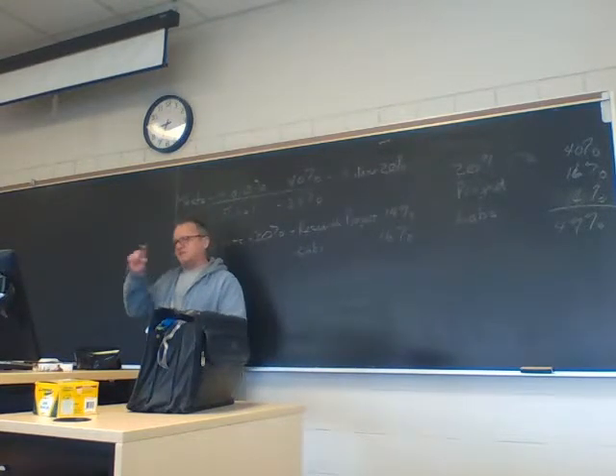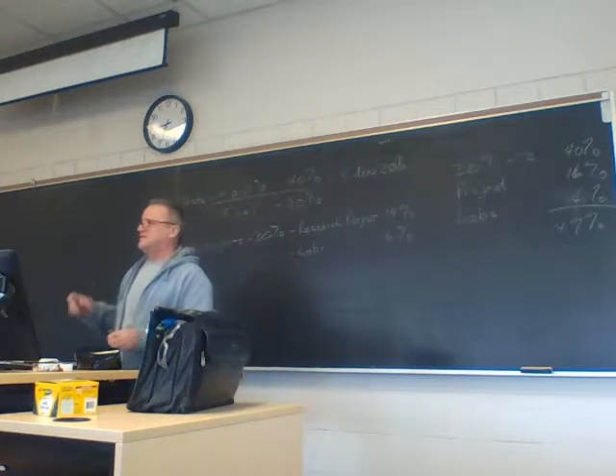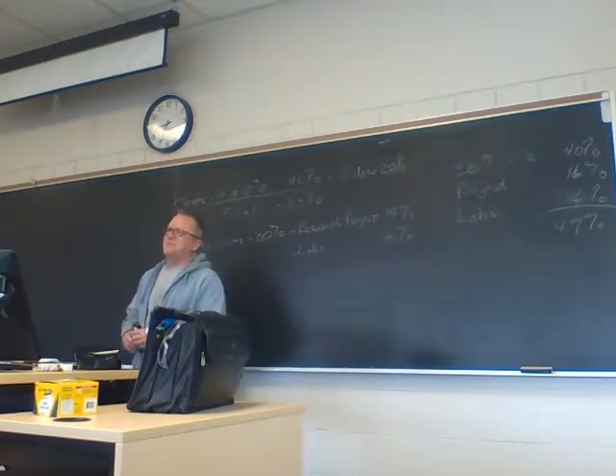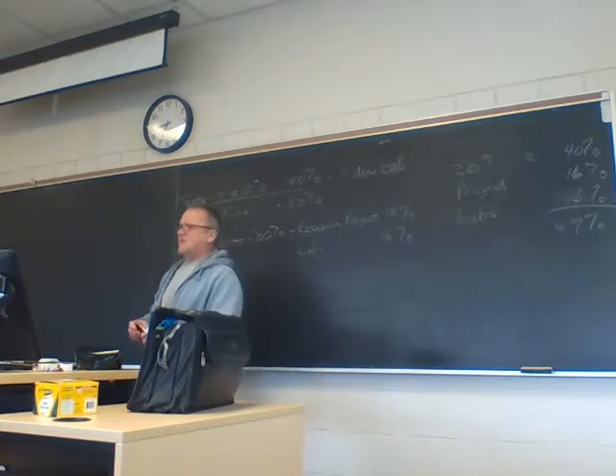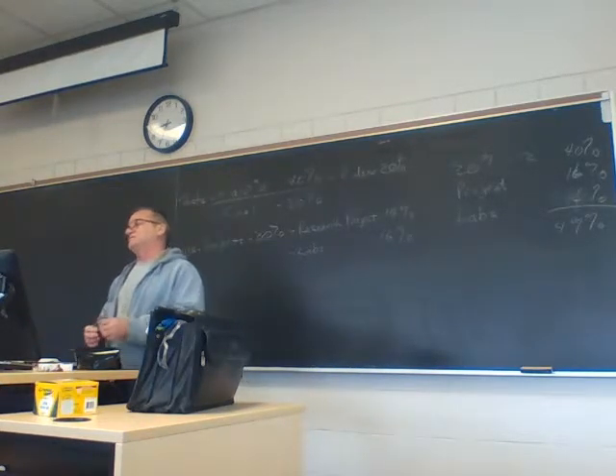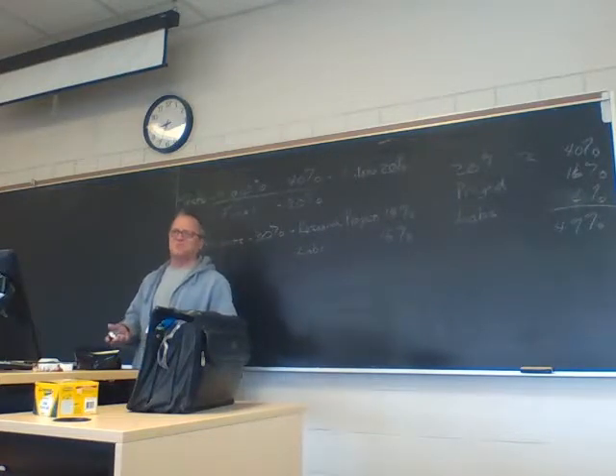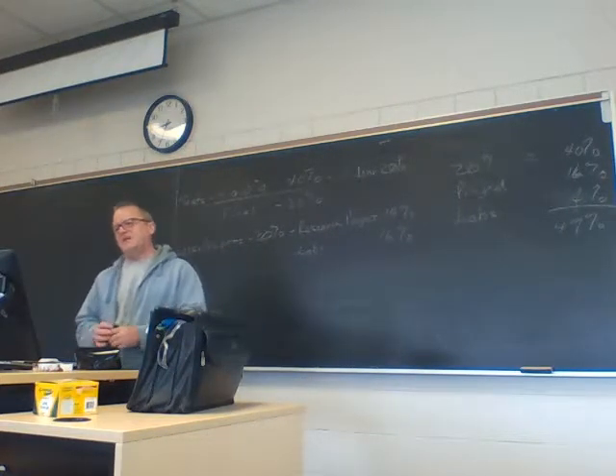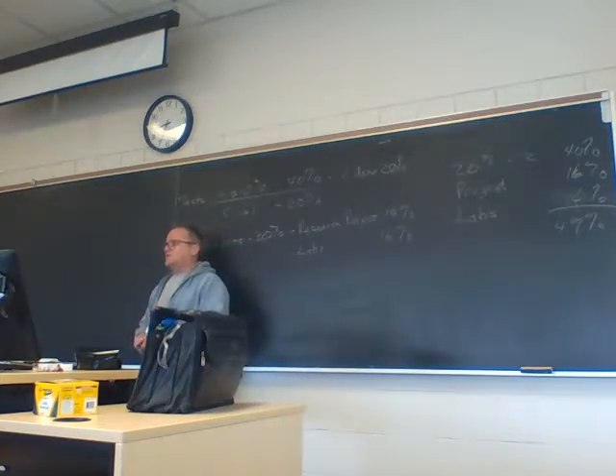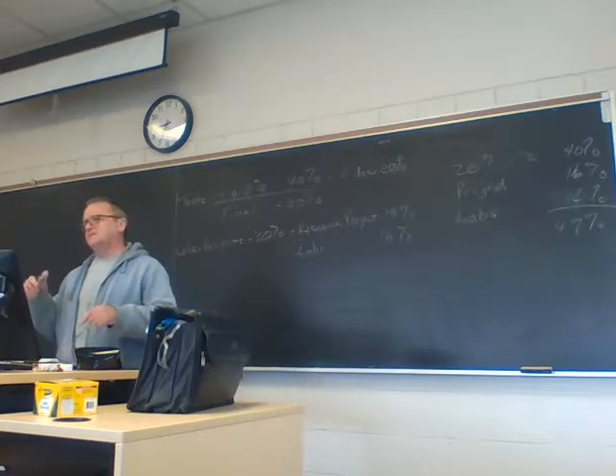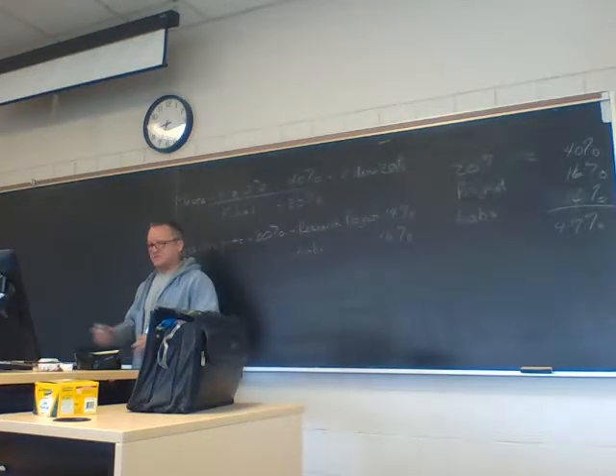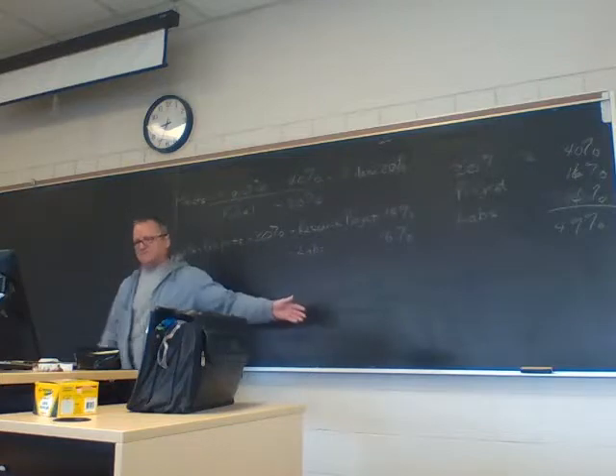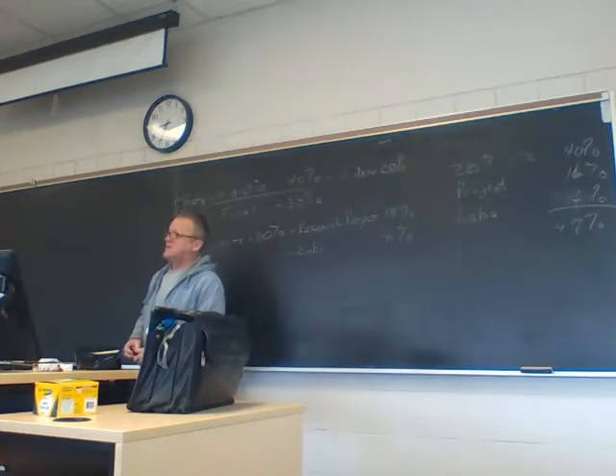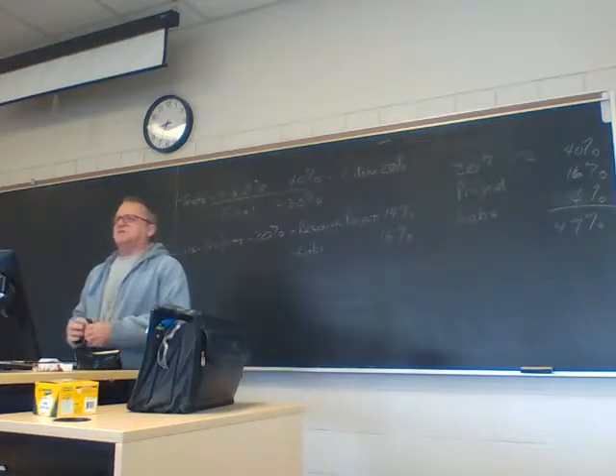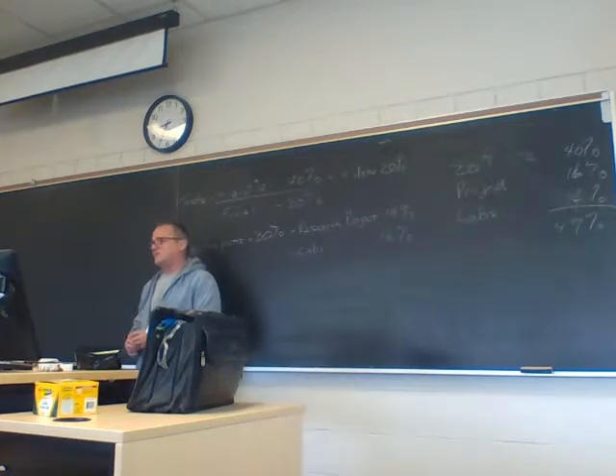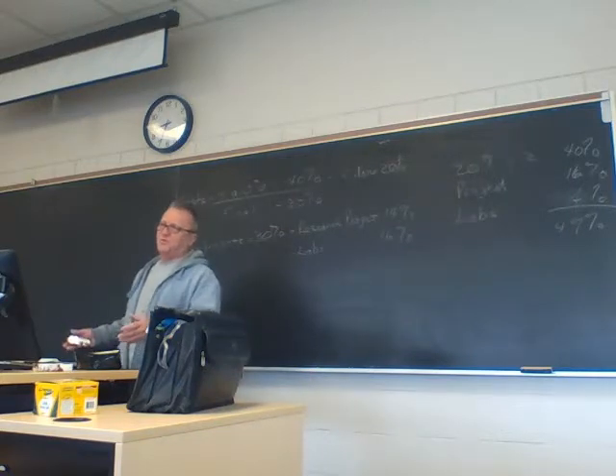So he went back to the guy he bought it from and said, no, it's not 600 volt. He should have gone and looked at it first before spending $20,000 or whatever. So we ended up getting a transformer to change it from 208 to 600. It's this wide, this high, and that deep. It's huge. So we have to figure out what it takes now to put this transformer on a 208 volt generator to supply 600 volt 3 phase into the building.